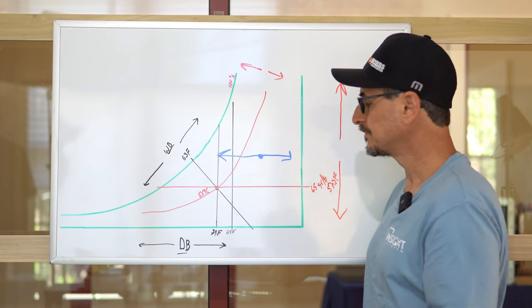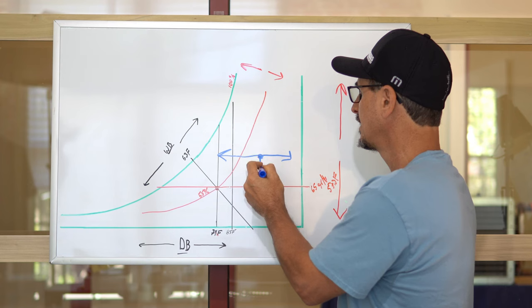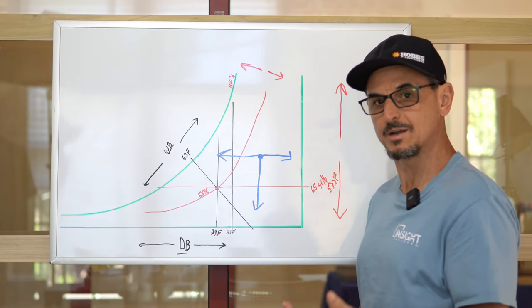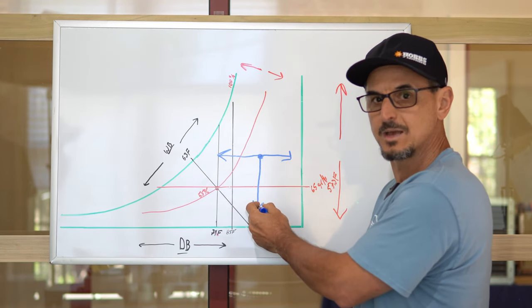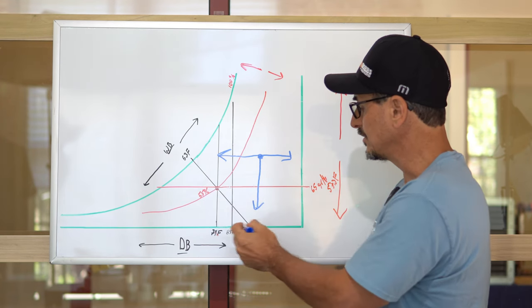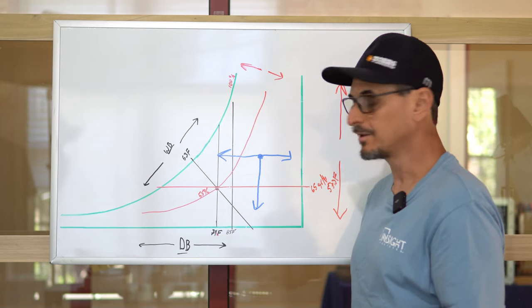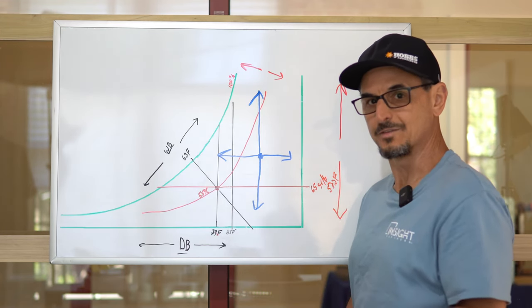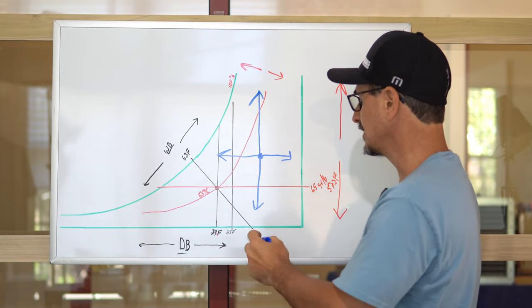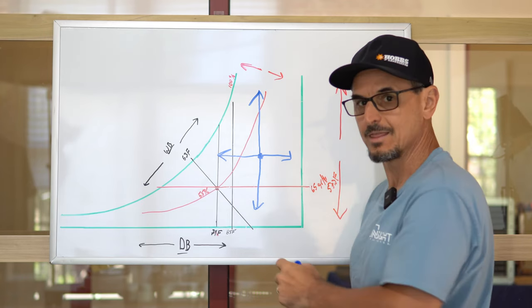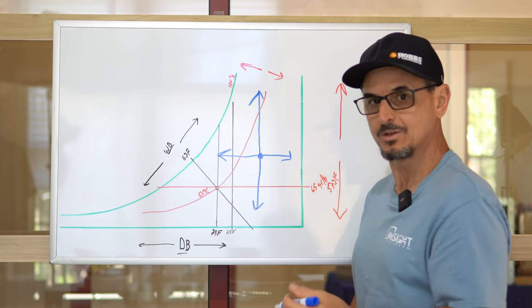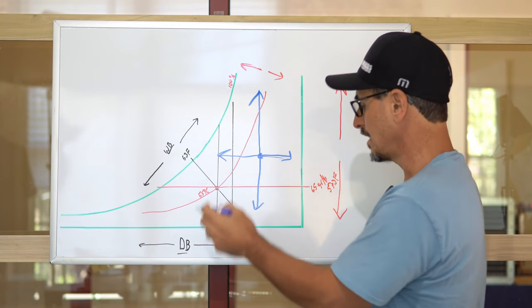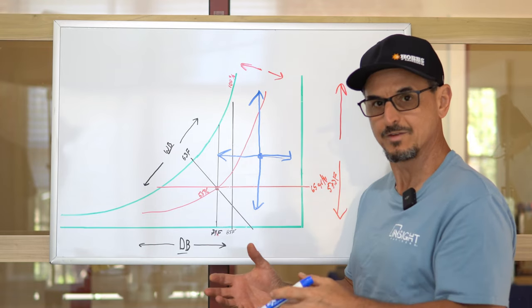If you take a point and go downward, that would be dehumidification — removing humidity. Moving from one point straight down to another, have we changed the sensible temperature? No — the dry bulb lines run vertically, so the dry bulb stays the same. If you take this air and go upward, that process is humidification — adding humidity. When you're going up and down, think humidity. When you're going left and right, think sensible temperature.